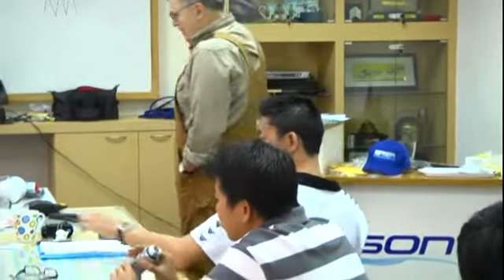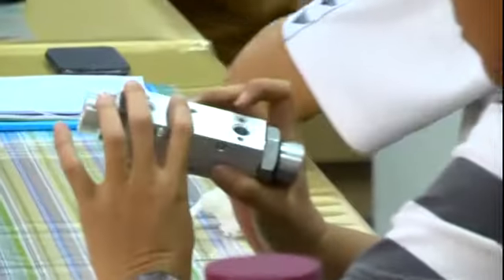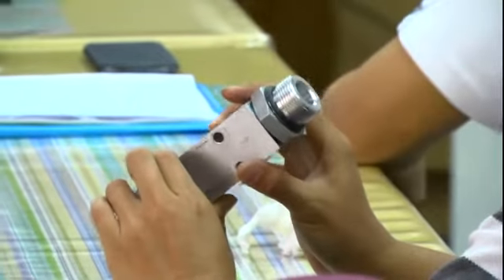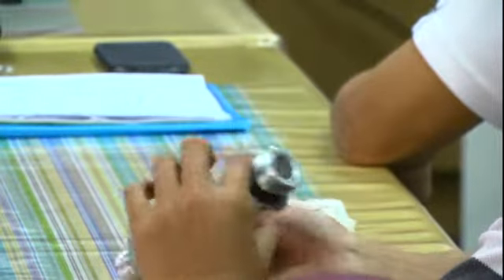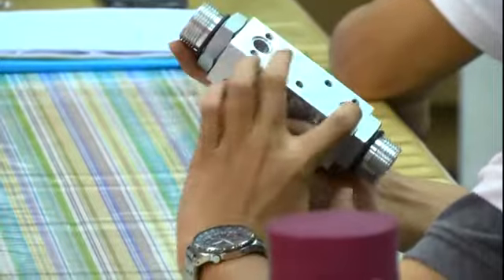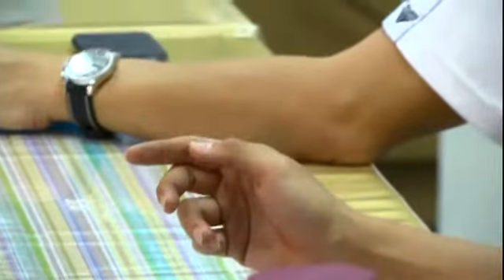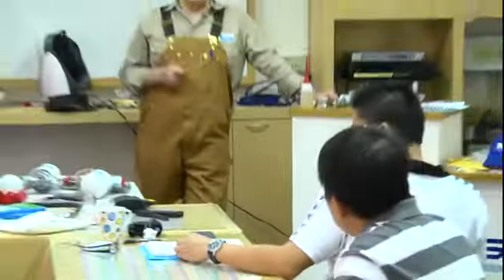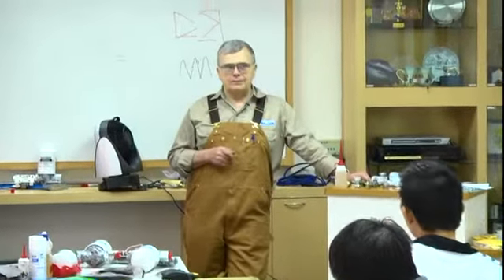The fittings on that, or the threaded part, those are yet another type of thread. That's an SAE straight thread, or what they call a running pitch thread. A running pitch means that there's no taper on it, and it requires an O-ring to seal it up.